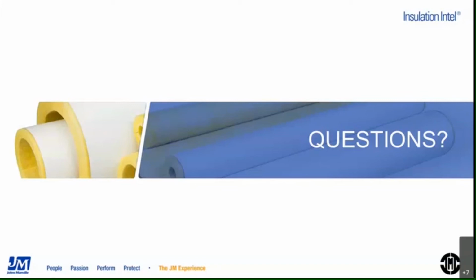All right, thank you. Greg, this next question is for you, and then Natalia, if you have anything to add, please do so. Please clarify the installation of pipe hangers to maintain the fire rating. Can the typical thermal block and hangers be outside the insulation, or do they also need to be internal to the insulation and the jacketing? Hangers need to be on the outside. That pipe has to be 100% sealed within that insulation all the way through. So all hangers need to be on the outside. Treat it like chilled water. Okay, all right, thank you.